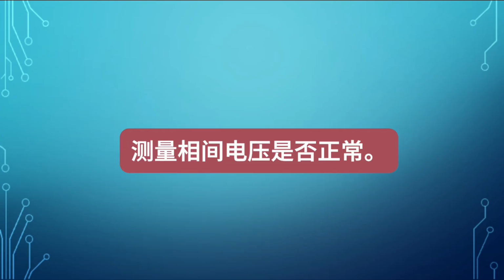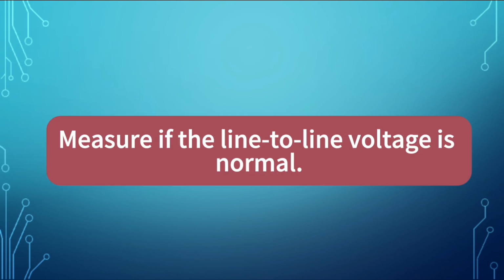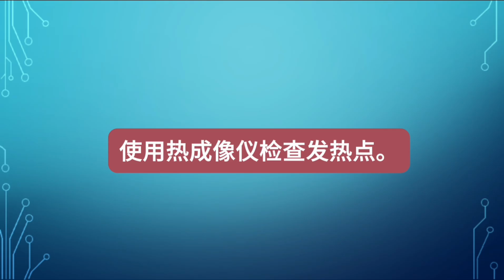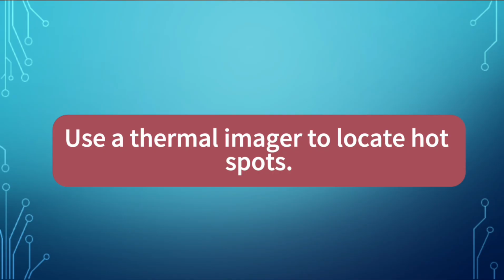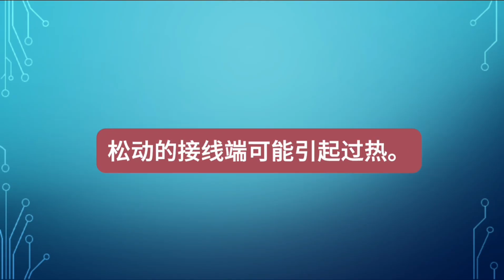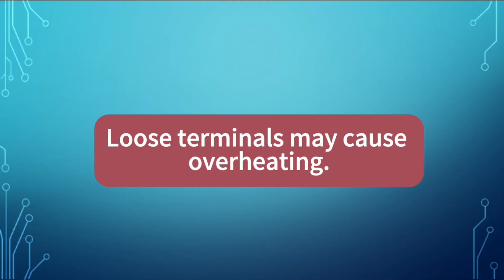Measure if the line-to-line voltage is normal. Use a thermal imager to locate hot spots. Loose terminals may cause overheating.